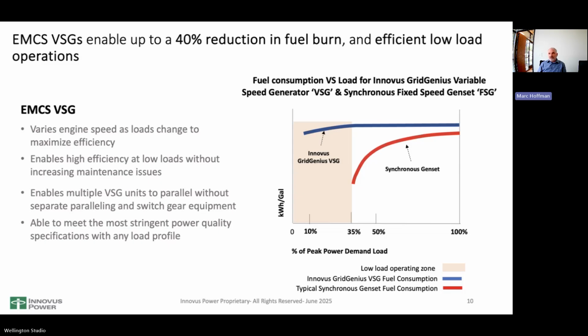And so that's why, for instance, every OEM, if somebody's going to run a diesel genset chronically below 35%, won't guarantee the engine because it's doing damage. So not only is there a penalty on fuel efficiency, there's a huge penalty in maintenance. And anywhere along that curve, once it starts dropping off, all the maintenance cycles that are planned or recommended for these gensets are based on this degradation of fuel, the average load that genset's going to run, and therefore parts just wear faster. Saying it another way, when an engine's run very efficiently, it has the least wear on it, even though that may seem counterintuitive.